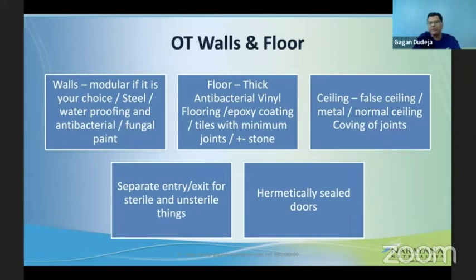You could have automated doors, ideally 2-wing doors, but a single door also works fine. A door is something you can go with whatever suits you, but it should be hermetically sealed in case you are putting in an AHU and want a positive pressure system, since any leakage will not let positive pressure develop.